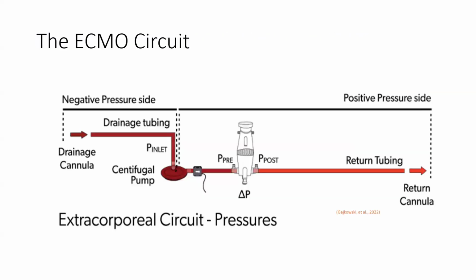Supporting patients on ECMO is really about plumbing. The circuit itself, we pretty much use an oxygenator that can supply 250 to 300 milliliters a minute per meter squared. So you're able to provide a baseline, or slightly more than enough, oxygen support for moderate amounts of exercise. ECMO includes a patient, plastic tubing, cannulas, a pump, and an oxygenator. The inlet side, the venous drainage, is a negative pressure into the system. The pump is drawing the blood to the pump through that tubing. That same pump is sending positive pressure forward to the oxygenator, where gas exchange occurs, and then out of the oxygenator through the return tubing to the return cannula.